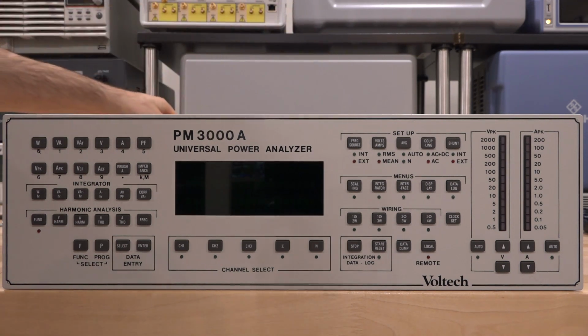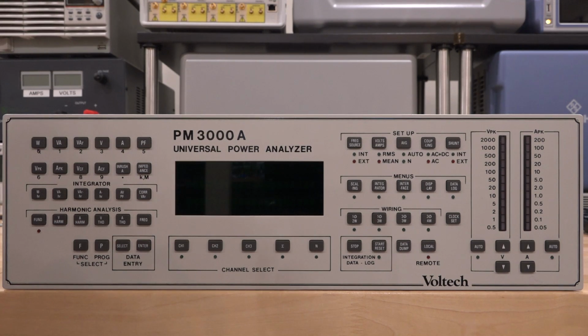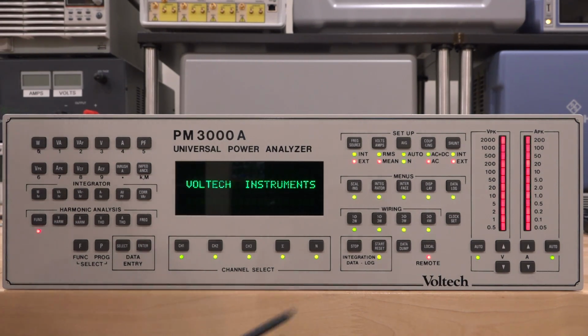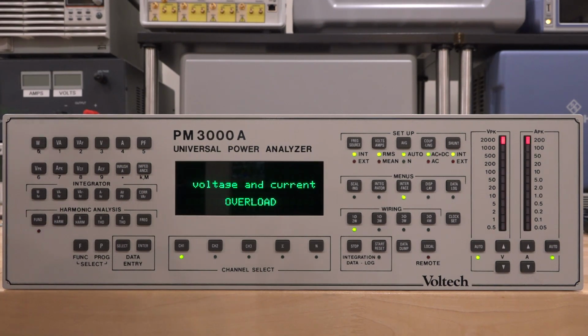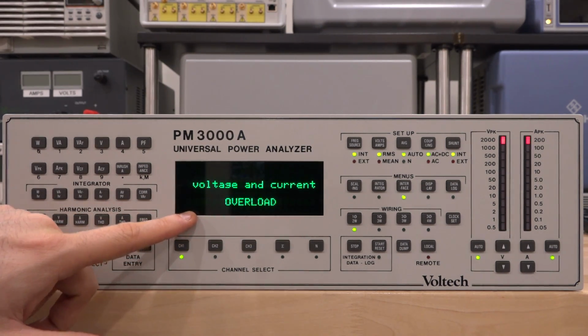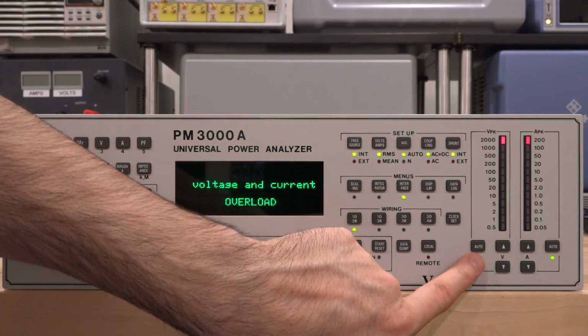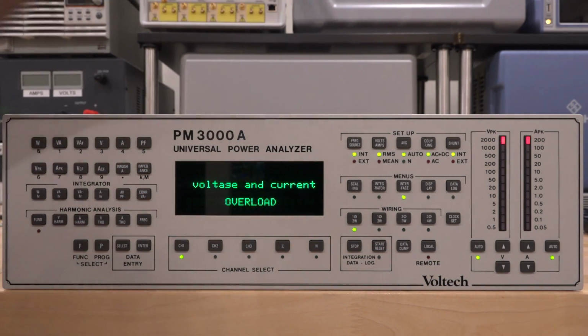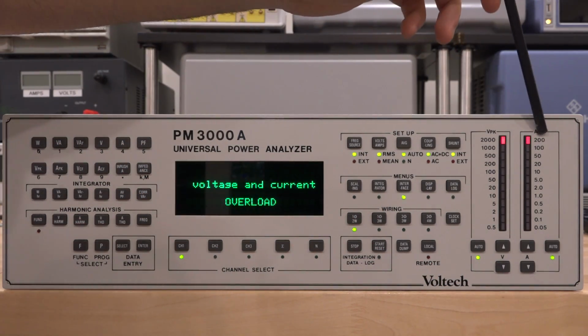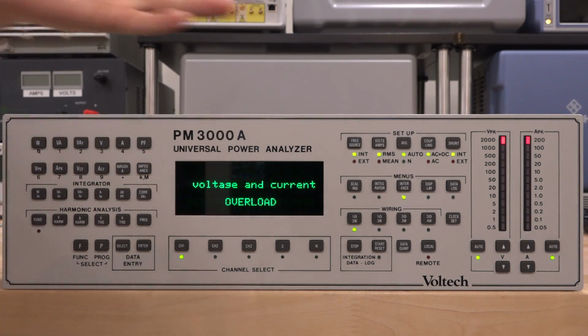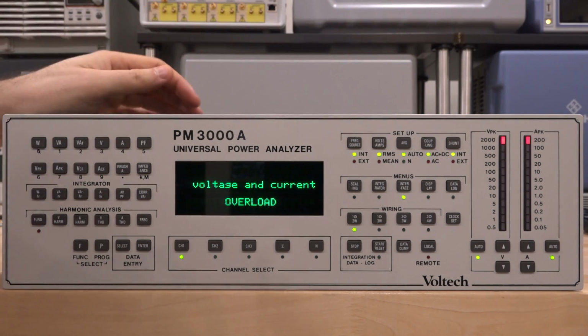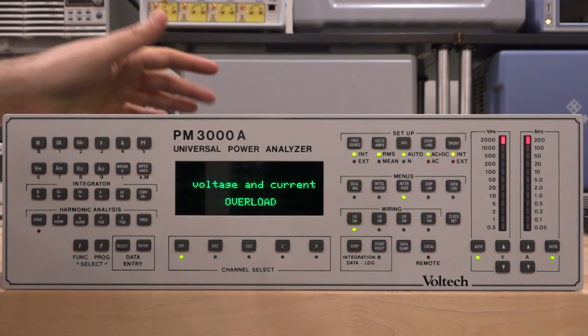So let's go and turn it on. There we go. Let's see what happens. It takes a bit of time. There it is, and you can see all the lights turning on. So indeed, the processor is working. I think I just saw firmware version 2.2, and then it just says a voltage and current overload. You can see under the auto condition, both of here, we have reached 2000 volt peak and 200 amp peak. And of course, there's nothing connected to this right now, so it shouldn't show anything. So something's definitely wrong with it.